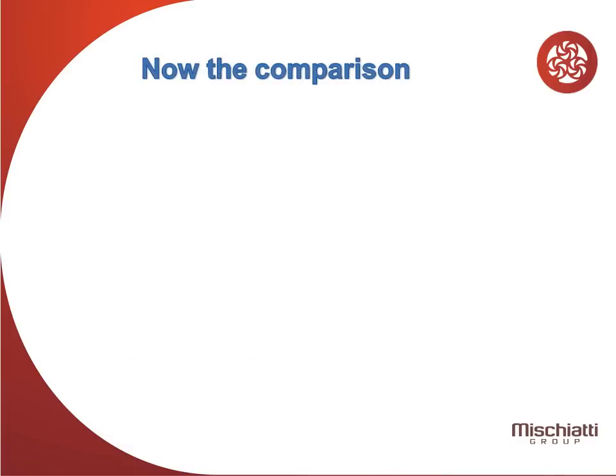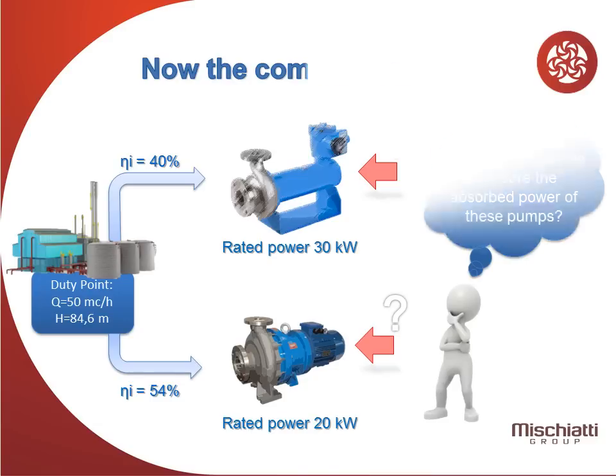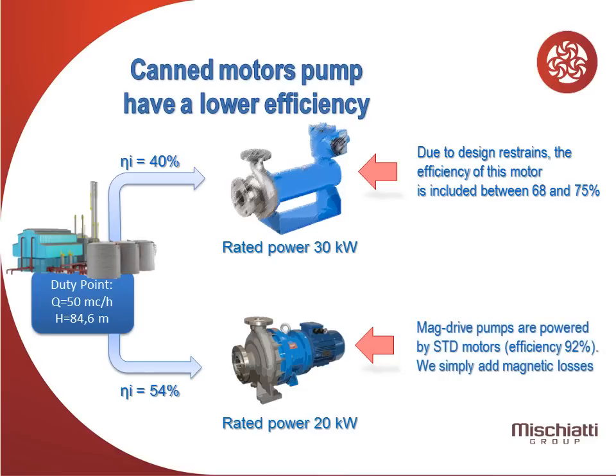Now the comparison. How can we compare the absorbed power of these pumps? Canned motor pumps have a lower efficiency. Due to design restraints, the efficiency of this motor is included between 68 and 75%. Mag drive pumps are powered by standard motors with 92% efficiency — we simply add magnetic losses.